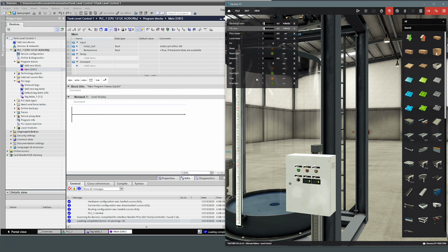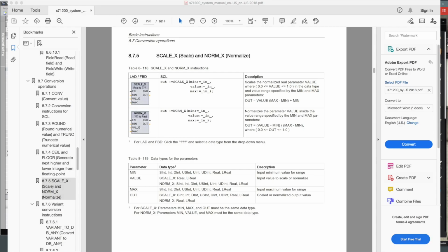Now, the way we do this is by using the conversion operations. Let's have a look at which instructions we will be using by having a look at the manual under Basic Instructions, Section 8. So the first instruction we will use is the normalize instruction, where we will read in the min and max values from the level meter that are given to us as voltages 0 and 10 volts, and we will normalize them to between 0.0 and 1.0 in real values.